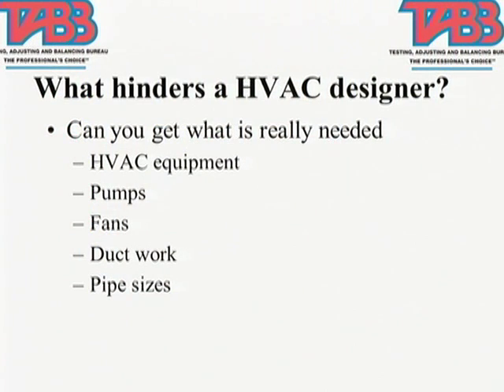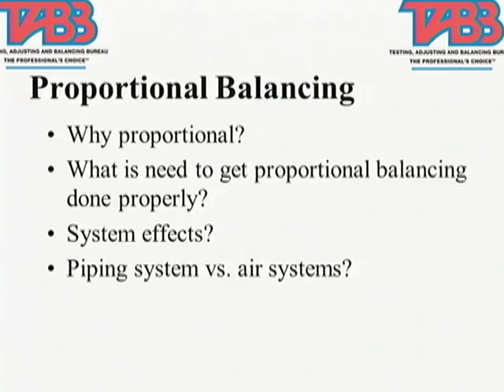And this was his way of value. He really thought he was value engineering it, as opposed to value engineering it for the good of the customer in the long-term use of that building. So you have 2 extremes of what value engineering is. So we talked about this, you can't get what you really need for equipment. Your pumps are the wrong size, your fans are the wrong size, your ductwork's the wrong size, and your pipes are the wrong size. So you need to have someone come in and balance it.